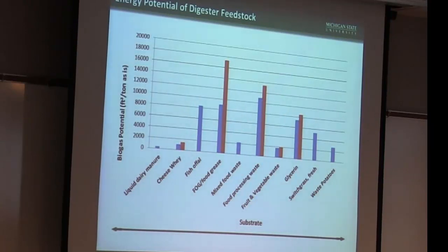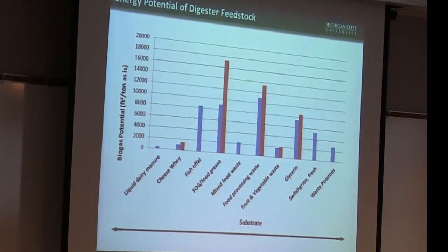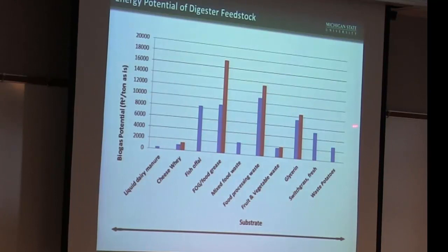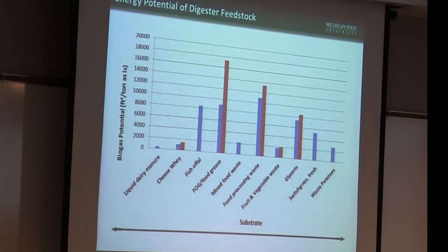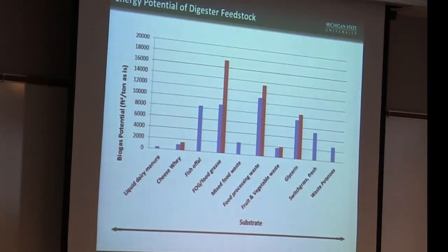The reason these outside materials are so important: looking at gas production potential in cubic feet per ton, manure is down at the bottom — about 30–50 cubic feet of biogas potential per ton. FOG has very high energy density. Food processing waste also very high. Fruit and vegetable waste much higher than manure. This is why we're so reliant on outside substrates — they are energy-dense compared to manure, which is microbial-dense. This has driven us to underperform a little bit in 2014, along with a lot of the mechanical issues.